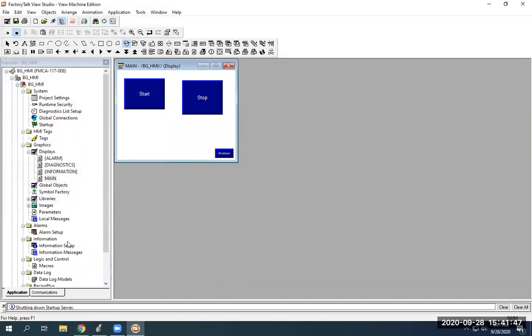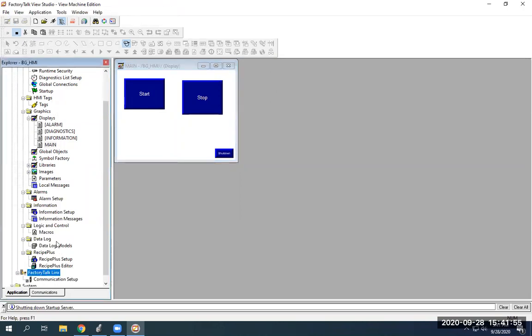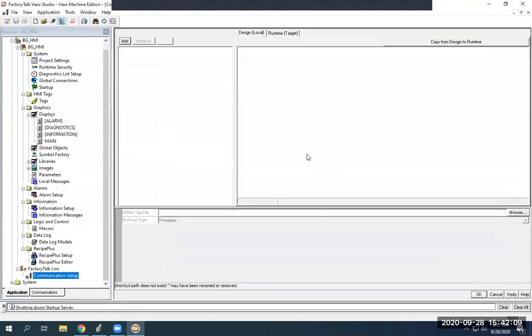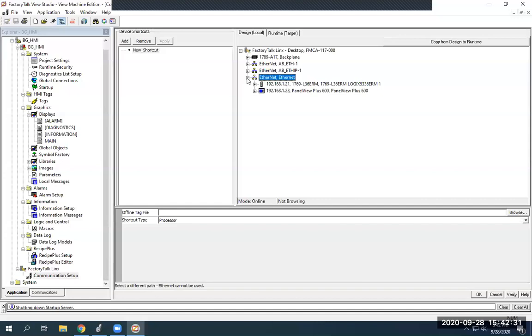I'll give them the tags here shortly, but in order to get ready to give them tags, we need to go down here to FactoryTalk Linx — that's your communication setup. You double-click on your communication setup and we're going to do a new configuration, so we're just going to hit Finish. It'll bring you to this screen where you'll see some options: backplane, Ethernet, AB, and all that. We need to create a device shortcut first. Within our FactoryTalk Linx network, 192.168.1.21 is our PLC which we are currently online with.